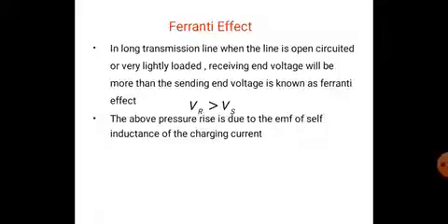The above pressure rise is due to the EMF of self-inductance of the charging current. So when a medium or long line is open circuited or lightly loaded, the receiving end voltage will be more than the sending end voltage. This phenomenon of rise in voltage at the receiving end of the open circuited or lightly loaded line is called Ferranti effect, because it was first observed by Sebastian Ziani de Ferranti in 1890.